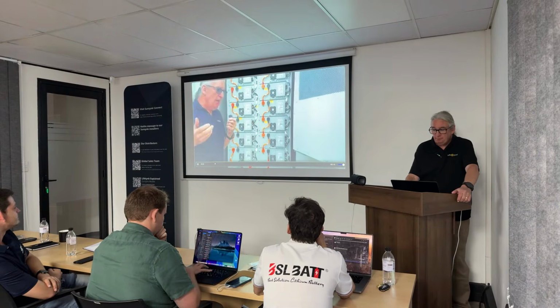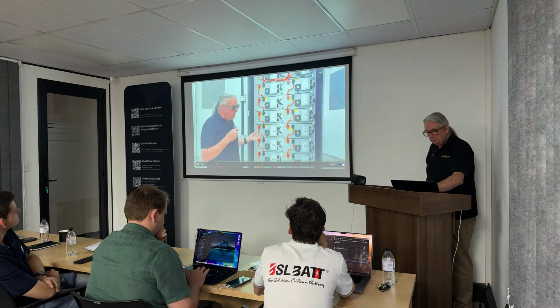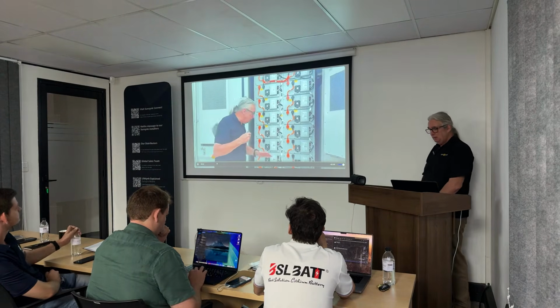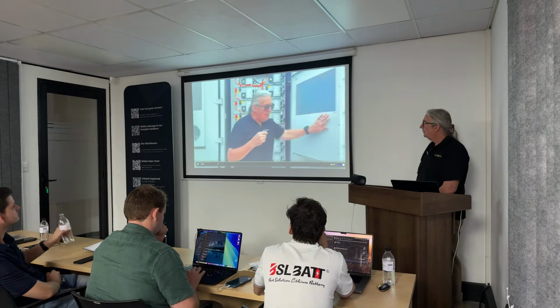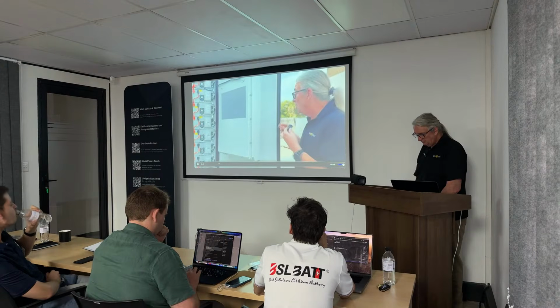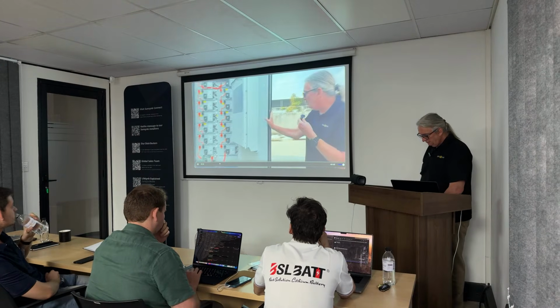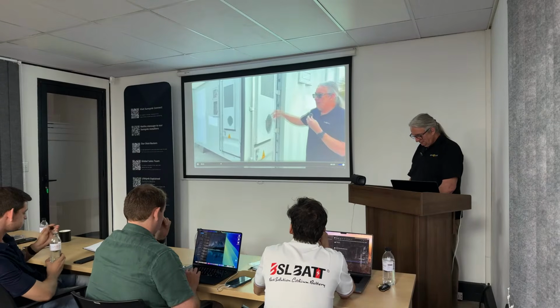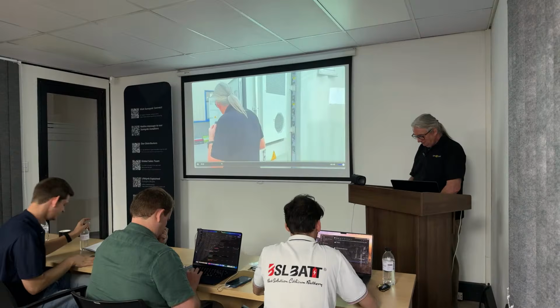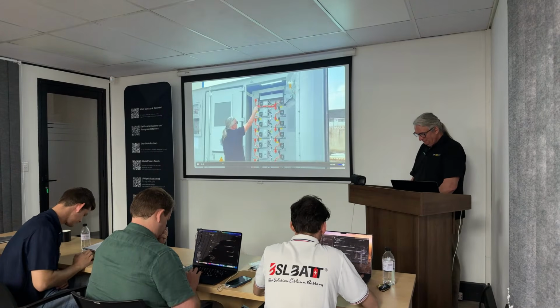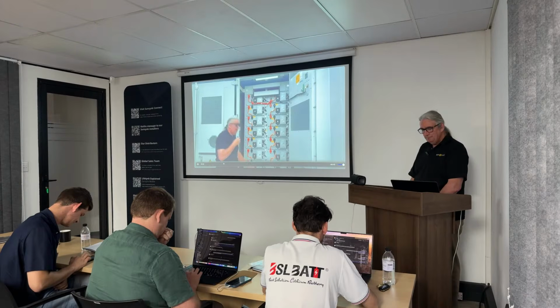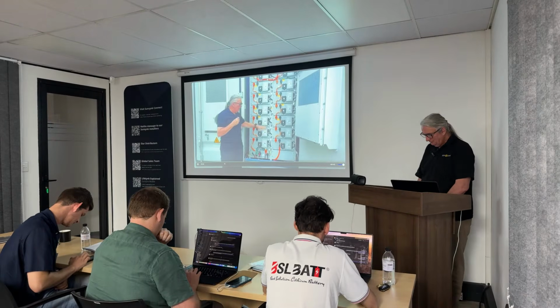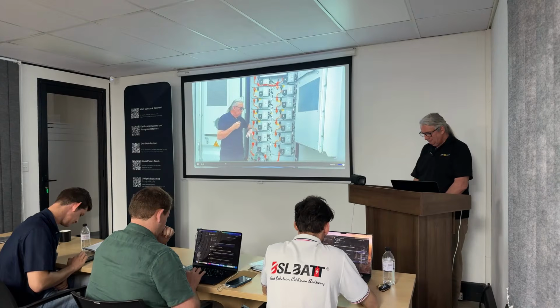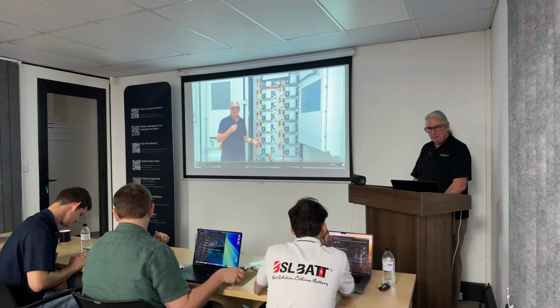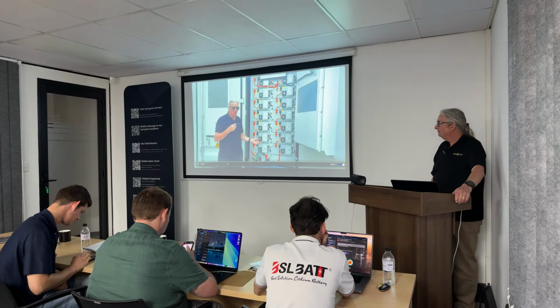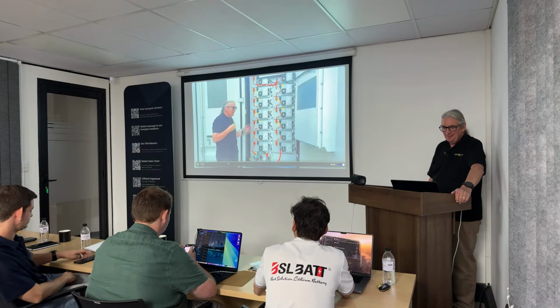We actually use air cooled rather than water cooled. People have a myth that air cooled just blows air into the batteries, but it doesn't - the HVAC units actually use a liquid internally to circulate on one side. Here we have the in and the out, and this circulates, and on the other side we circulate the air through, going through the ducting of the battery and coming back out. The nice thing about this method is we haven't got pipes and clips and water flowing everywhere. In the UK, most of the time it's cold enough anyway, so we don't need a cooling system, and you don't need to add the parasitic losses.